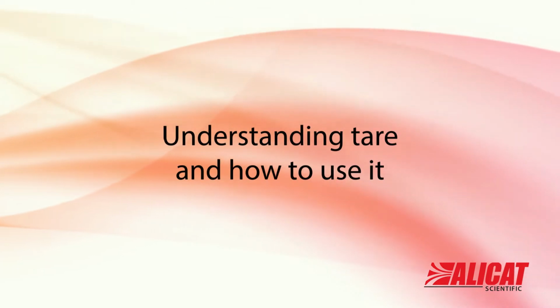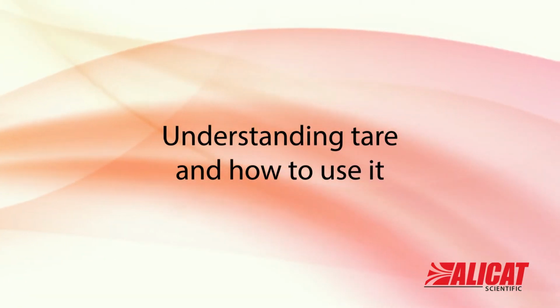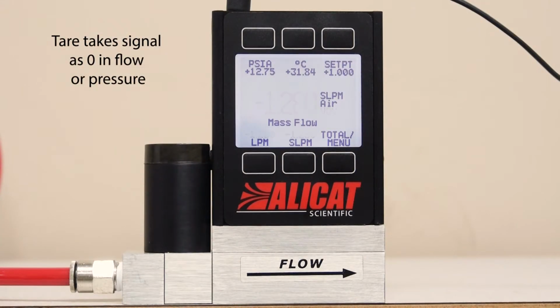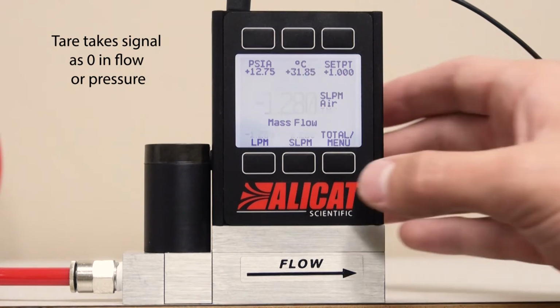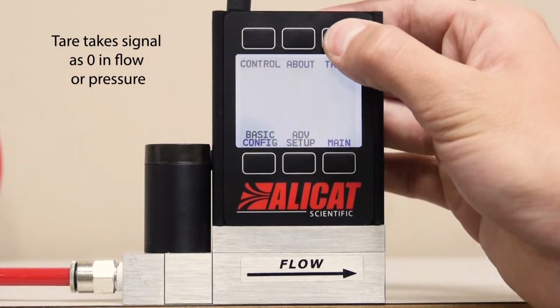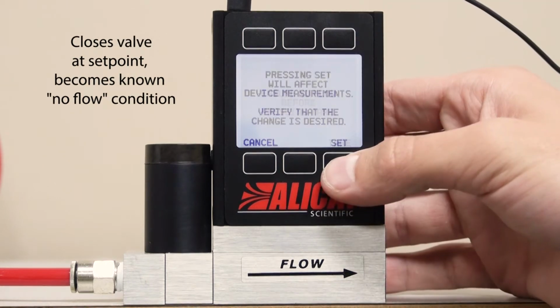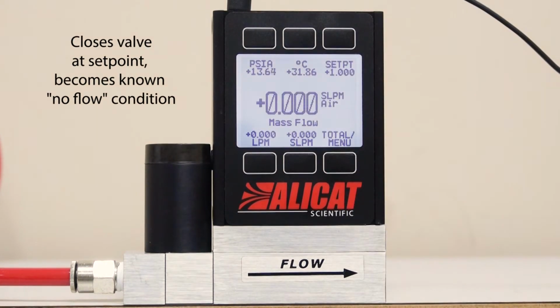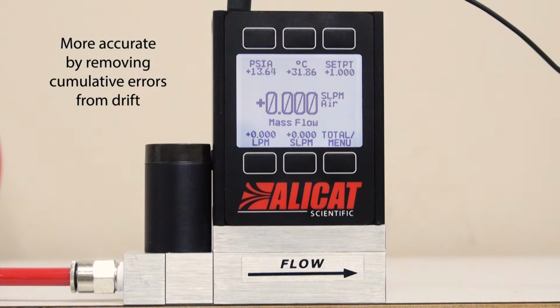What is tare, why is it important, and how do I use it? The tare function on Alicat flow controllers lets the instrument take a detected signal as 0 in either flow or pressure. A 0 set point results in the closing of the valve and a known no-flow condition. This feature makes the device more accurate by periodically removing any cumulative errors associated with drift.